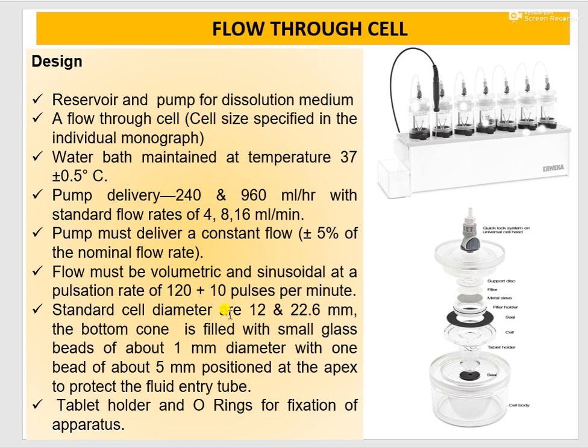Now standard cell diameters are 12 and 22.6 millimeter. The bottom cone is filled with small glass beads of about 1 millimeter diameter, with one bead of about 5 millimeter positioned at the apex to protect the fluid entry tube. Means the bottom will be filled with 1 millimeter diameter beads, while the apex will have a 5 millimeter bead. The role of bead is to maintain the flow of your dissolution medium.